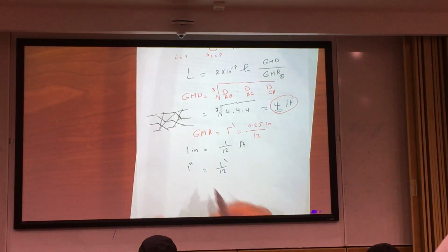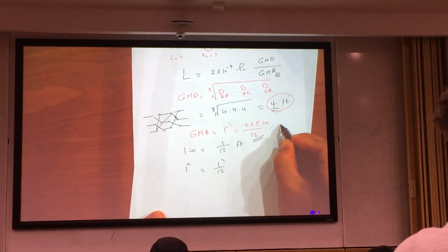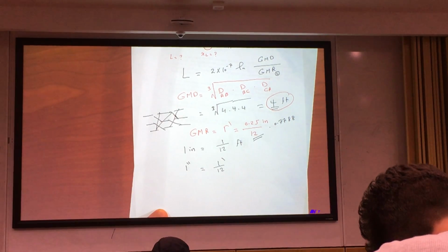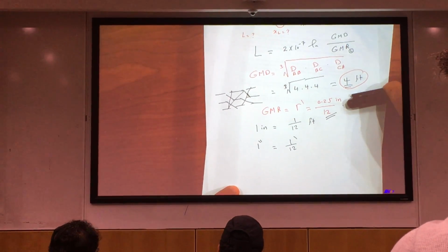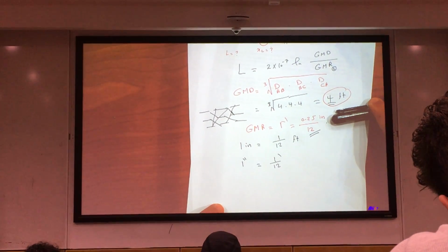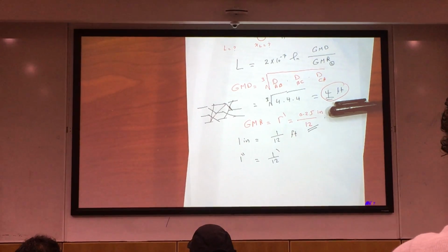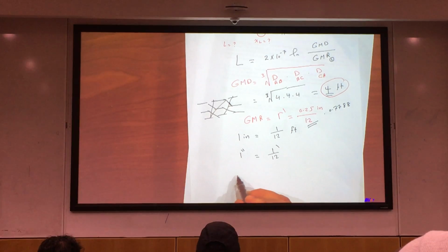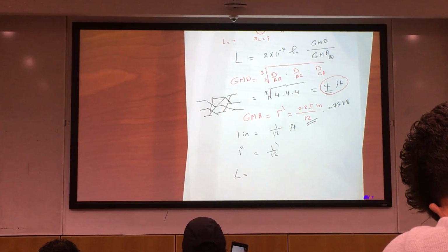So the geometrical mean radius is equal to R multiplied by 0.7788, which is e to the power minus 1 over 4. If I'm calculating capacitance, I will not use this. And that's the only difference between calculating GMR for capacitance and GMR for inductance. Then you use your formula, L, to calculate it. So that's number 3.